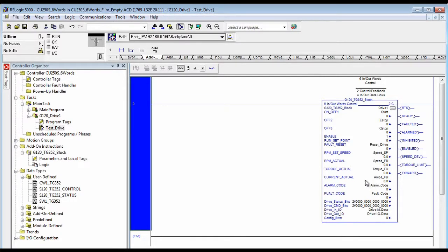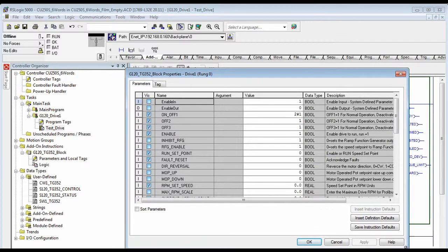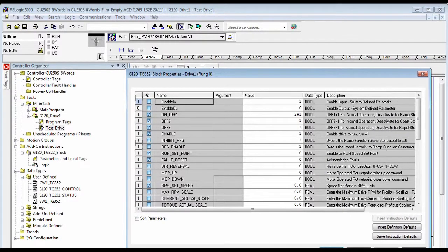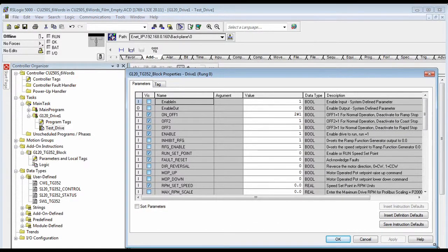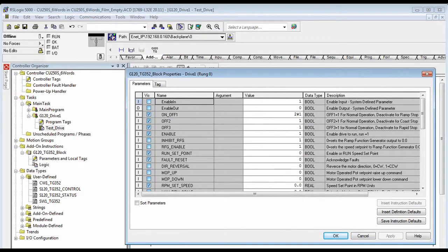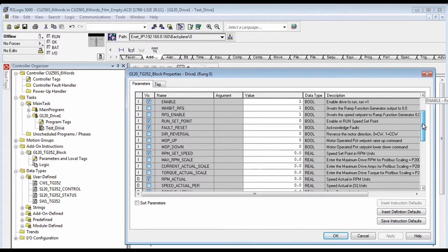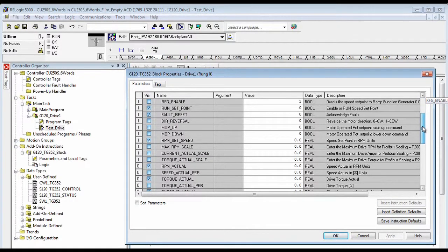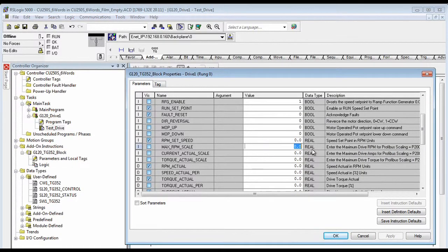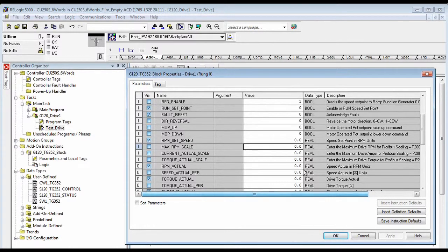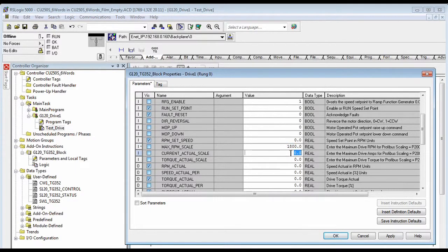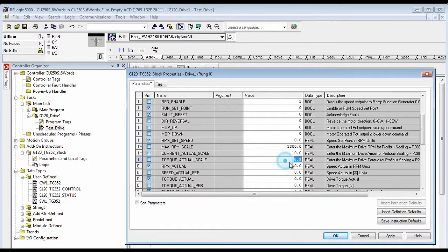Next, we need to set a few parameters in the block for scaling. The scaling values can be found in the drive itself if you don't know what they were. So we scale what the maximum RPM is, what the maximum current was. I'm just using some basic values here.